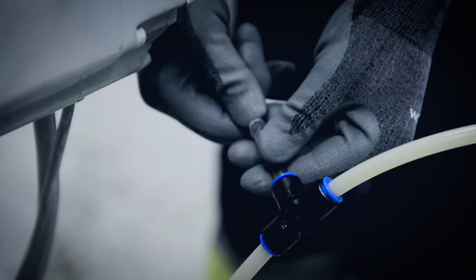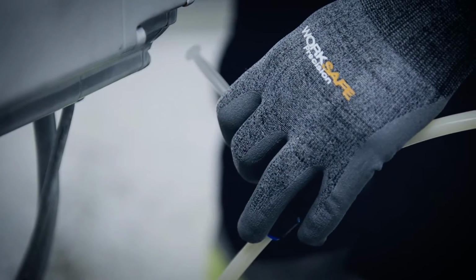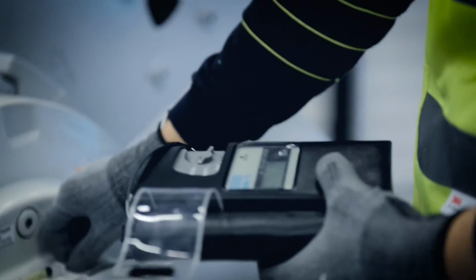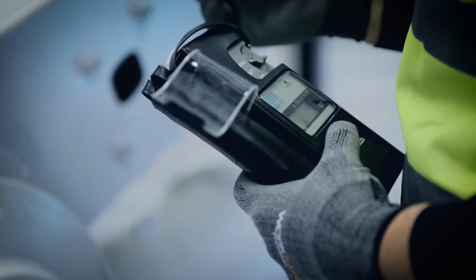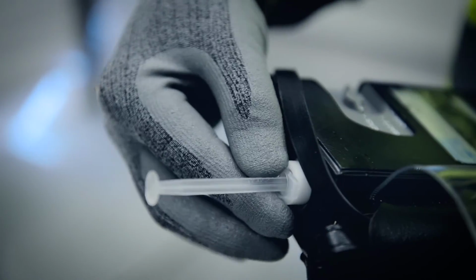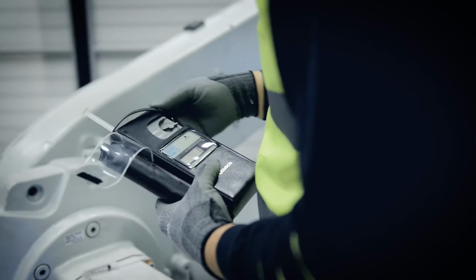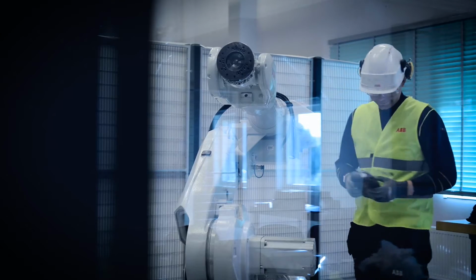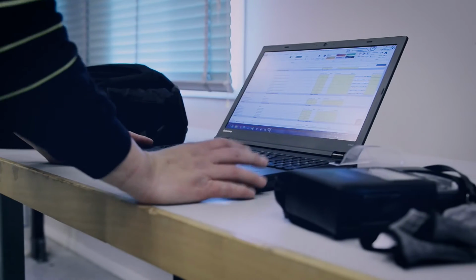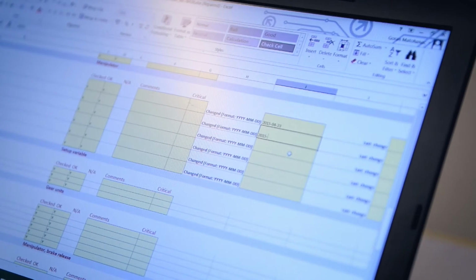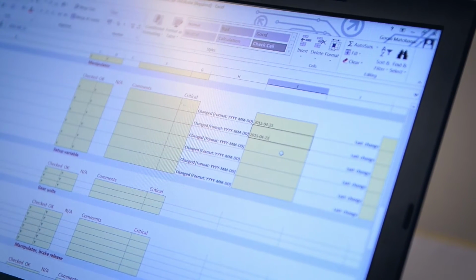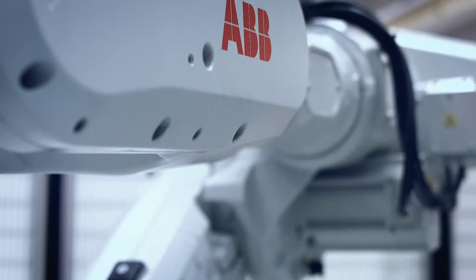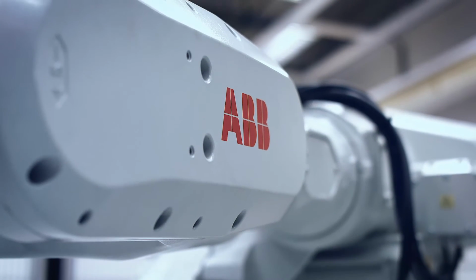As part of the inspection, we test the oil condition by taking a sample with a syringe. After checking if the oil is clear and doesn't smell, the next step is to measure the amount of steel dust in the oil, signs of which can indicate bearing or gear damage. Once the reading has been taken and entered in the maintenance report, a color-coded traffic light system aids yet again in the identification of potential issues.